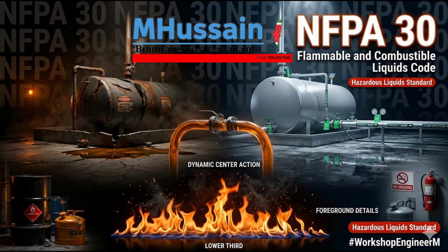And that is precisely when low-expansion foam water sprinkler systems become mandatory. Instead of just cooling and diluting, foam uses advanced fluid mechanics. How does that work mechanically? The system injects a specialized synthetic foam concentrate, usually an aqueous film-forming foam, or AFFF, into the water piping before it hits the sprinkler head. When that pressurized mix hits the air at the nozzle, it aggressively expands into a thick, aerated blanket.